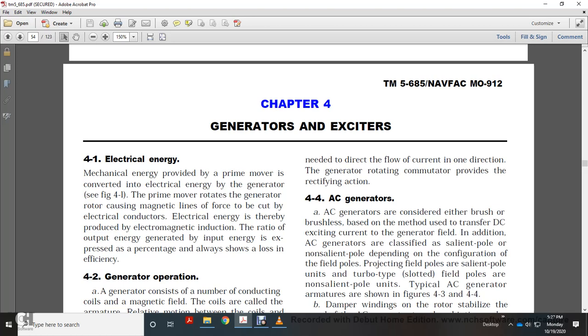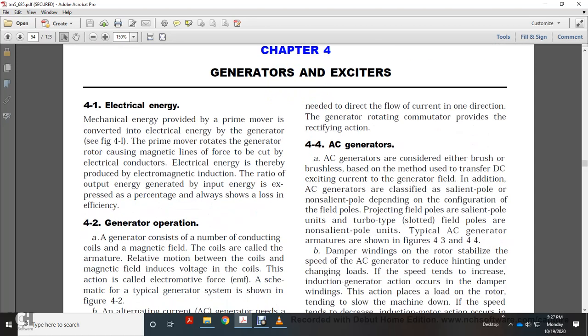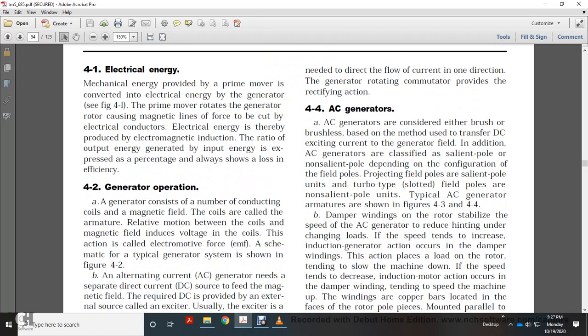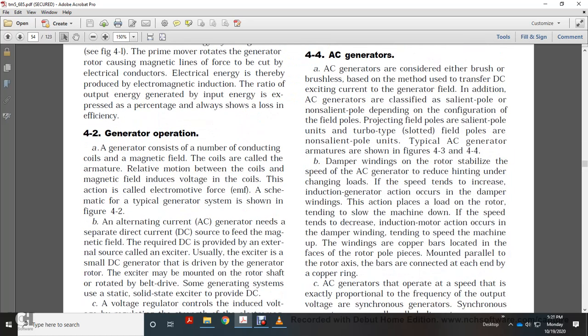Alright, 4.4, AC generators. AC generators are considered either brushless or brush type, based on the method of transfer of the DC excitation current to the generator field. AC generators are also classified as salient pole or non salient pole, depending on the configuration of the field poles: projecting field poles for salient pole units, and turbo type, with slotted field poles, for non salient pole units. Typical AC generators are shown in figures 4.3 and 4.4. Damper windings on the rotor stabilize the speed of the AC generator to reduce hunting under changing loads, and induction generator action occurs with the damper winding.